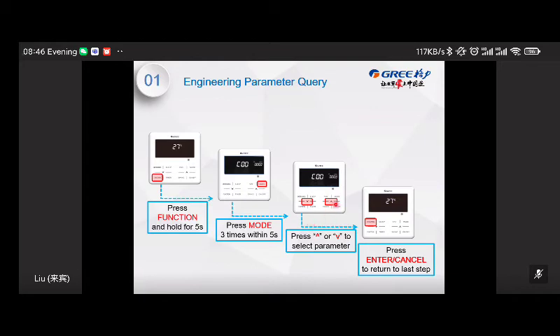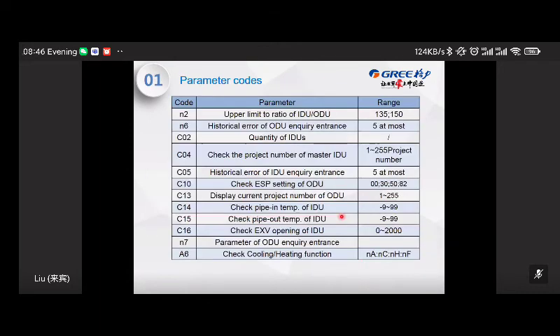Okay, press up and down to select the parameter. And here are the parameter codes you can find in engineering checking. This is the upper limit ratio of indoor units and outdoor units. Okay, it's the historic error. You can find five error codes for the history at most. C02 is the quantity of indoor units. C04 is the project number of master indoor units. Yeah, you can find the address of that indoor unit.